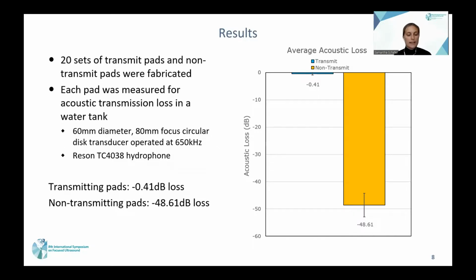The transmitting pads averaged -0.41 dB loss, and all of the non-transmit pads met the required -40 dB loss with an average of -48.61 dB. And you can see here in the graph that with the standard deviation, we had some that reached even higher than that, over 50 dB as well.